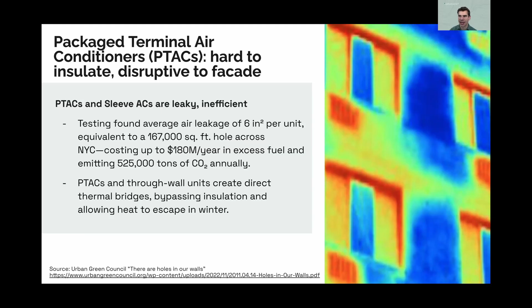This thermal camera image is from a report called 'There Are Holes in Our Walls,' about the state of PTACs in New York. It shows how the sleeves for PTACs lose a lot of thermal energy and leak a lot of air, creating holes in the facade of buildings. The report estimated the energy loss from this. When older buildings install a heat pump and remove the radiator, this is often the approach taken, but it ends up wasting a lot of energy through the hole.